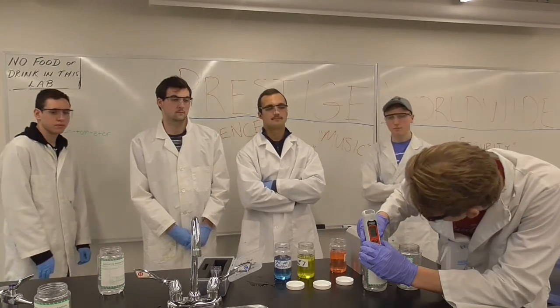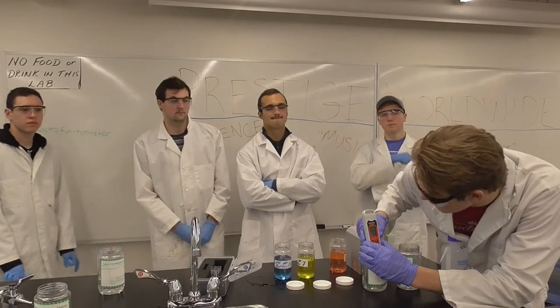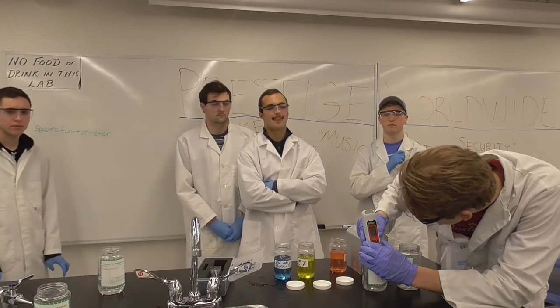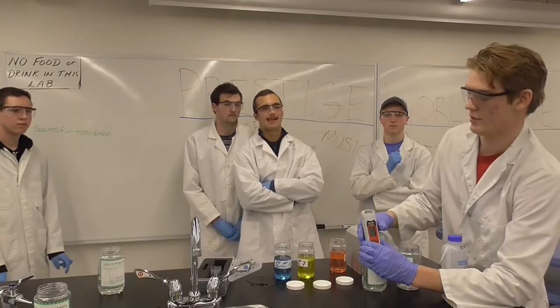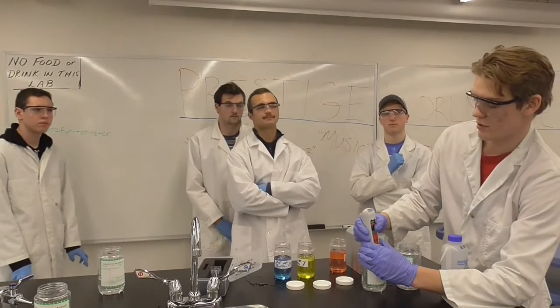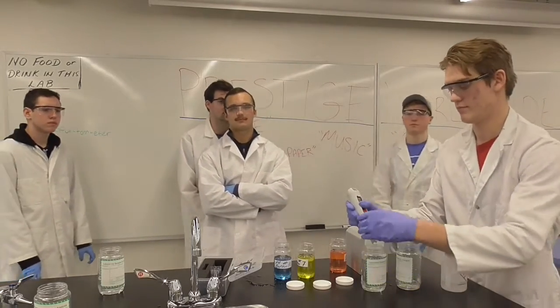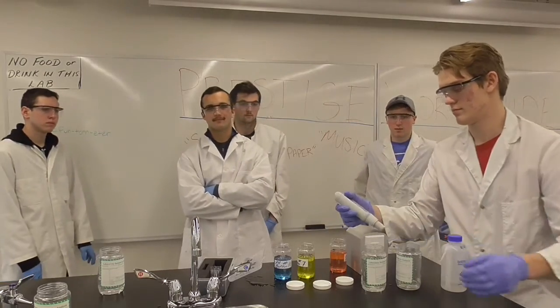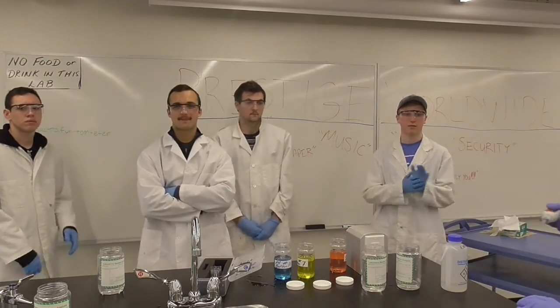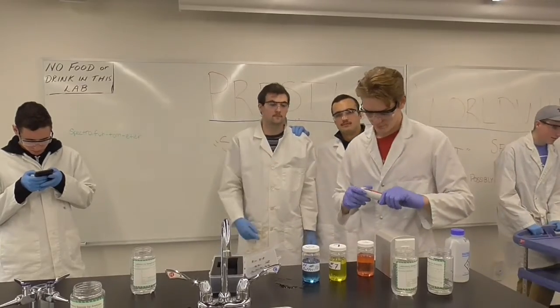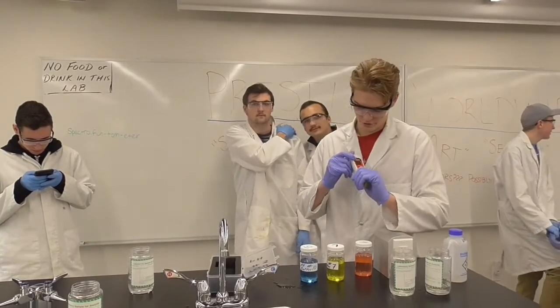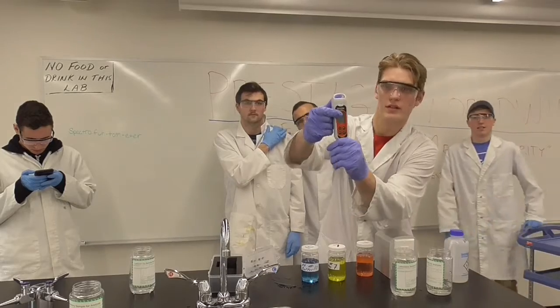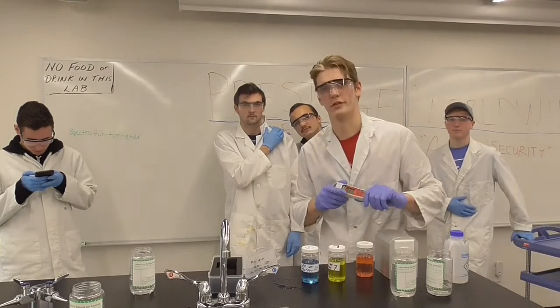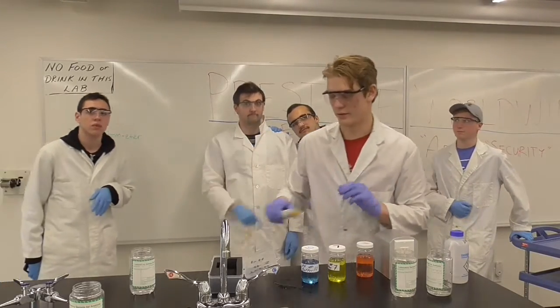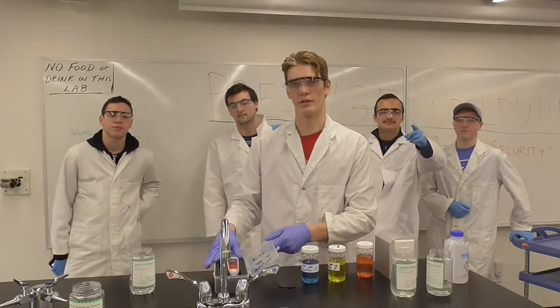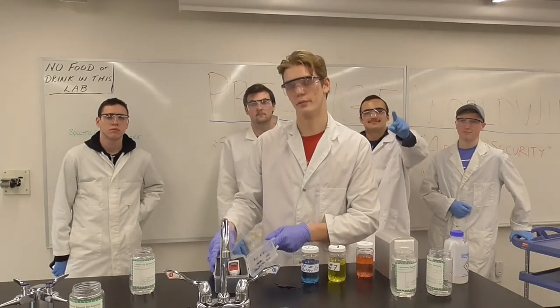So this water is 7.55, and it's got a temperature of 20.9 degrees Celsius. So yeah, that's the pH of the water. Nice. Yeah, but they can move. And just to show you, the battery level is right there, and if the battery level is ever low, you should consider charging up before you take it into the field. And remember to recalibrate for every different water source that you go to.